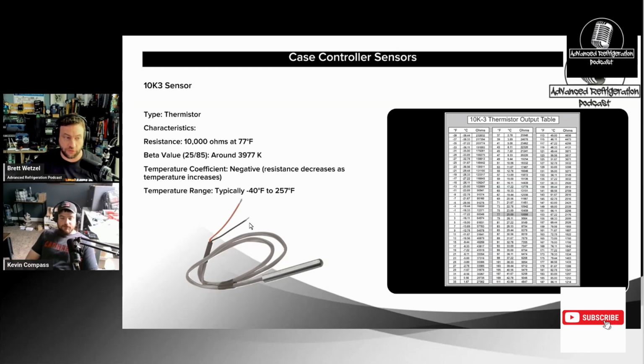The other thing is, you want to check it at both ranges because you don't know if the guy that was there before you just put a different sensor in, like a 10K2 and 10K3. So check it at room temperature, but then also check it on the lower end in the ice water. I usually start with checking it at the board just to see what it is. If it's reading all funky numbers or not reading at all, I start at the board. And if I have no ohms and it's open, or if it's shorted, then I will move on to the case and isolate it there and check the sensor.